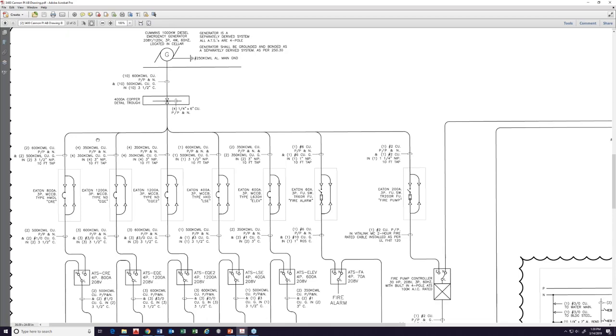Now, they are not being protected from short circuit by the downstream device. The downstream device will protect it, in essence, backwards on an overload condition. So if there would be an 800-amp device, for example, this will limit the load to 800 amps. Therefore, it provides overload protection for the upstream conductor as well. But in a short circuit condition, because it is only 10 feet, it is enough to shut down the generator controller package. And that's how these conductors are protected. But you would have to follow the tap rules. And I hope I answered the question.